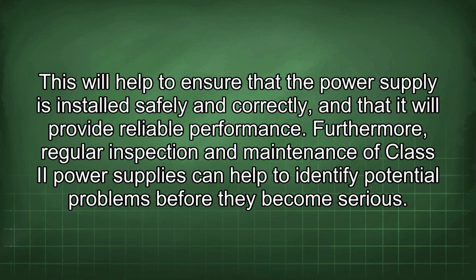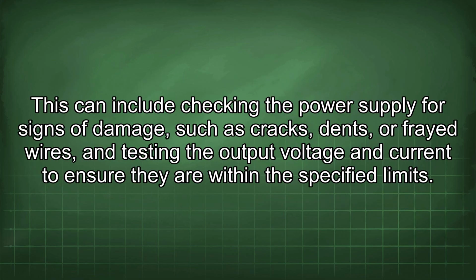This will help to ensure that the power supply is installed safely and correctly, and that it will provide reliable performance. Furthermore, regular inspection and maintenance of Class II power supplies can help to identify potential problems before they become serious. This can include checking the power supply for signs of damage, such as cracks, dents, or frayed wires, and testing the output voltage and current to ensure they are within the specified limits.